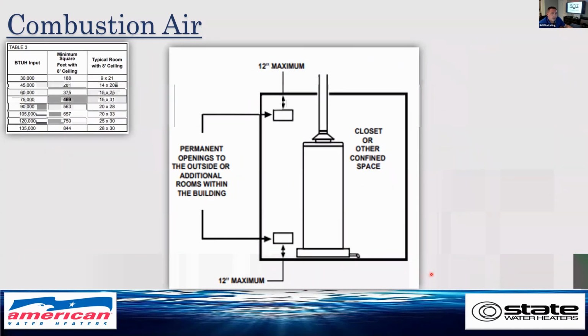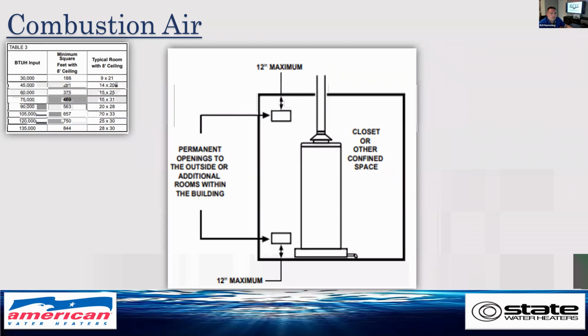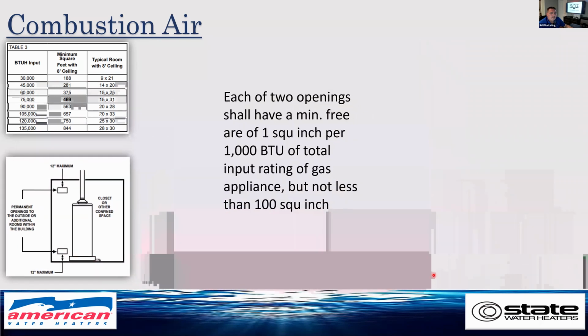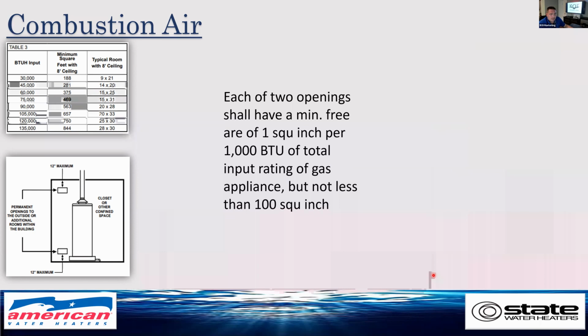So if we don't have the correct makeup air or combustion air, we need to bring it in through a permanent opening from outdoors or another room. And we accomplish this by installing high and low grills into the wall. Each opening shall have a minimum free space of 1 square inch per 1,000 BTUs of total input for the gas heater, but not less than 100 square inches, meaning a 10 by 10 is the smallest you can use.